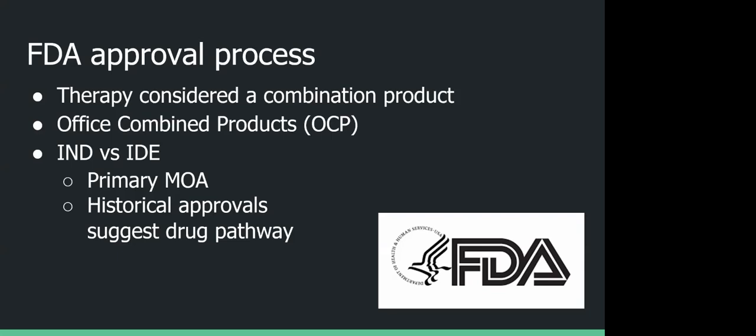Generally, you only need to file either an IND, an investigational new drug application, or an IDE for a new device. The designation is based off the primary mode of action, so whichever, either the device or the drug, impacts the treatment the most. For SDT and photodynamic therapy, photodynamic therapy has historically gone through the drug pathway. They say the primary mode of action is through the drug: the light activates the drug, and so it's the drug.